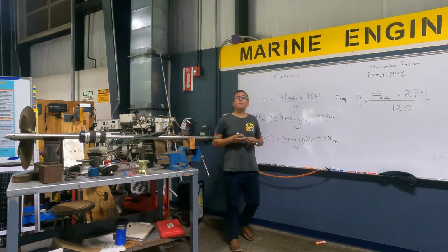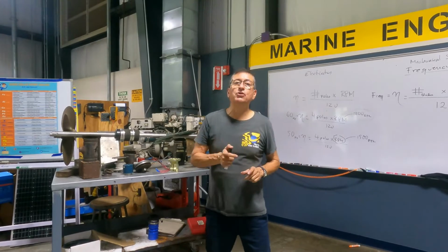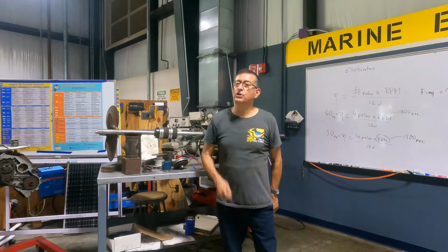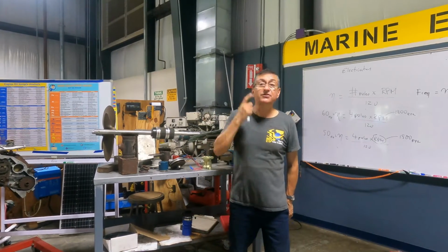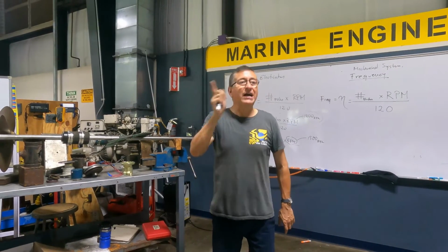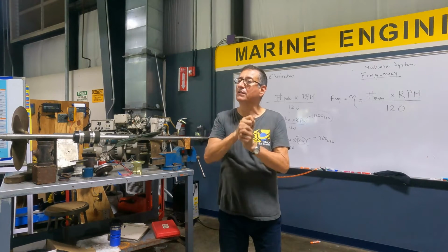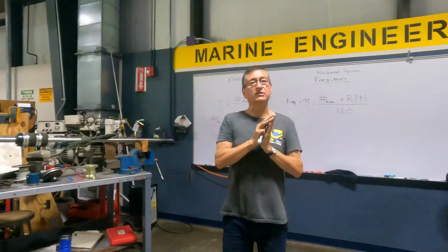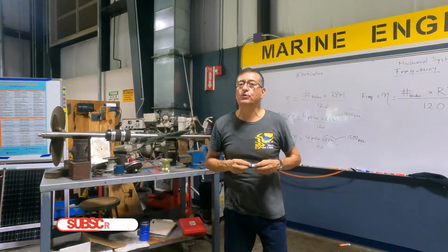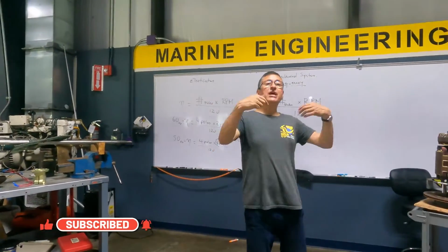The generator in a boat that produces American power at 60 hertz should be rotating at 1800 RPMs, constant. This is why you hear that the generator does not adjust the RPMs. The RPMs are constant in order to keep the frequency constant. How much should the rotation of a European generator be to produce 50 hertz? 1500. Okay, good.